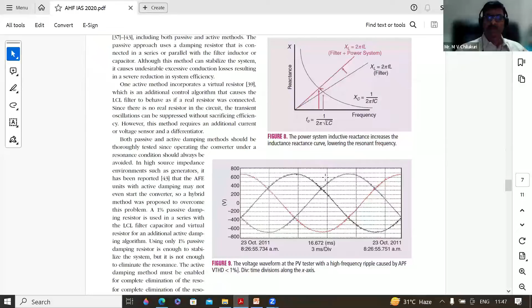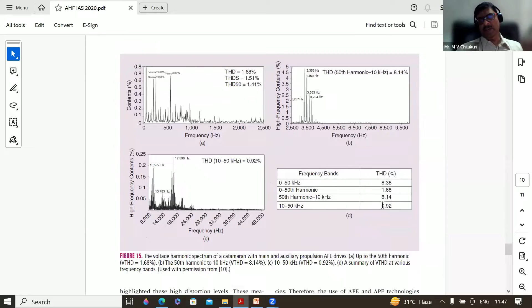If you measure up to the 50th harmonic, THD comes to 1.68. But if you measure with a new instrument that can go up to 50 kilohertz, for example the Fluke 1775 or 1772, the THD shown is 8.38. If you measure with another instrument covering up to 10 kilohertz, you get yet another value. So there is significant variation in accuracy depending on the instrument and the algorithm being used.